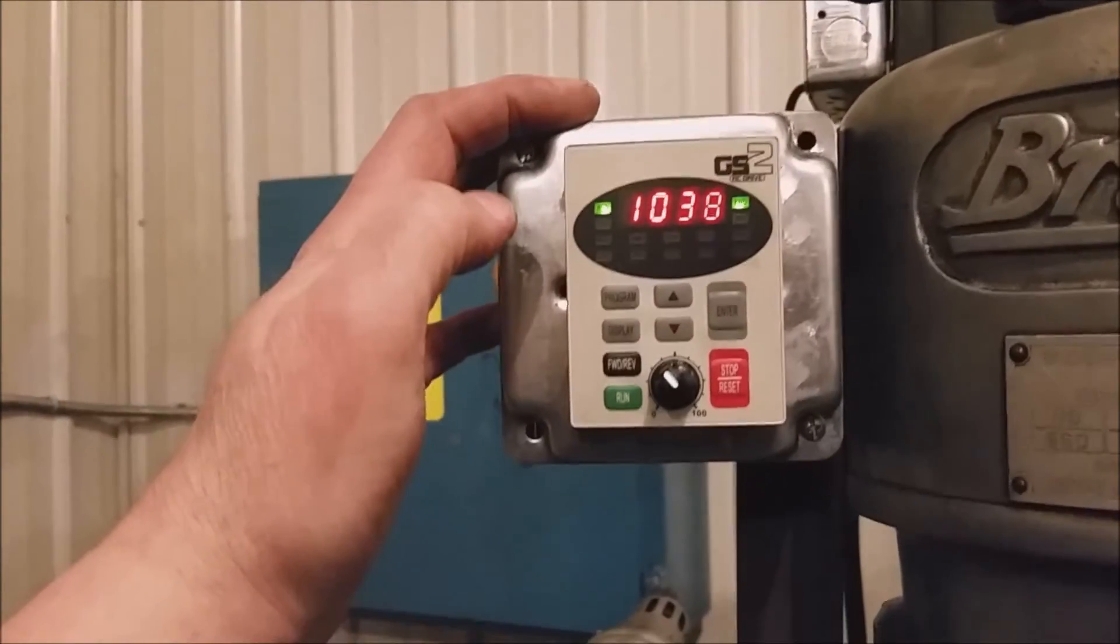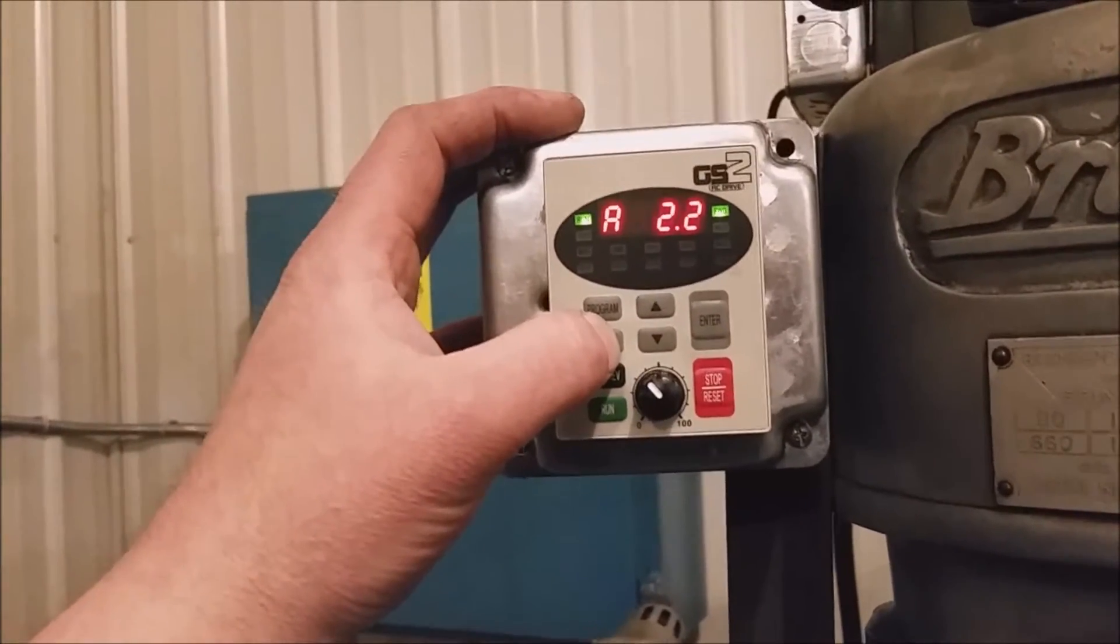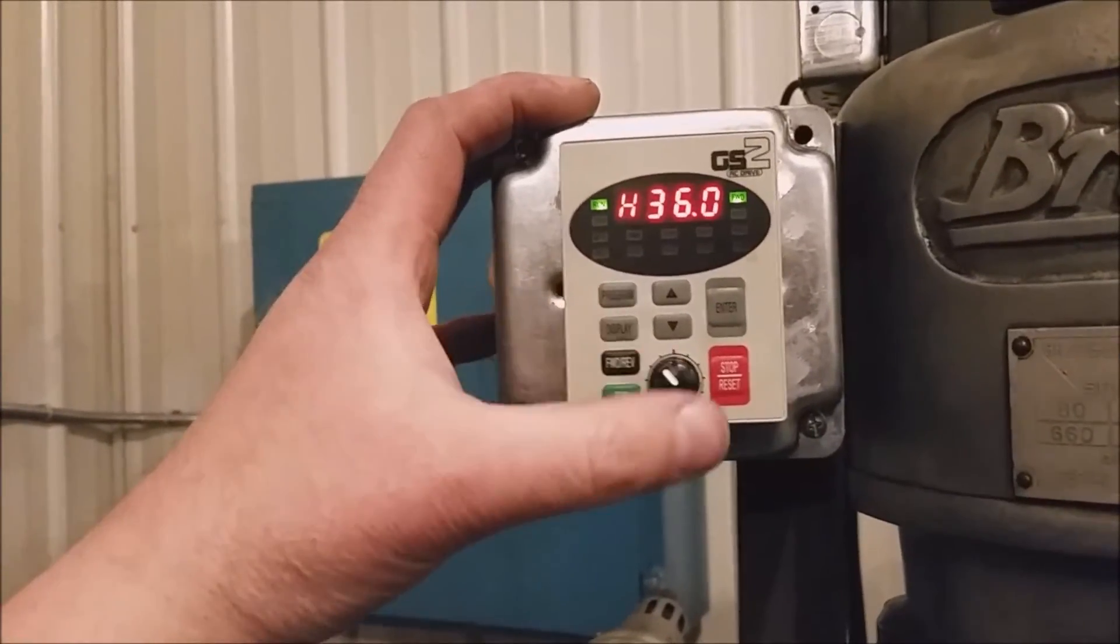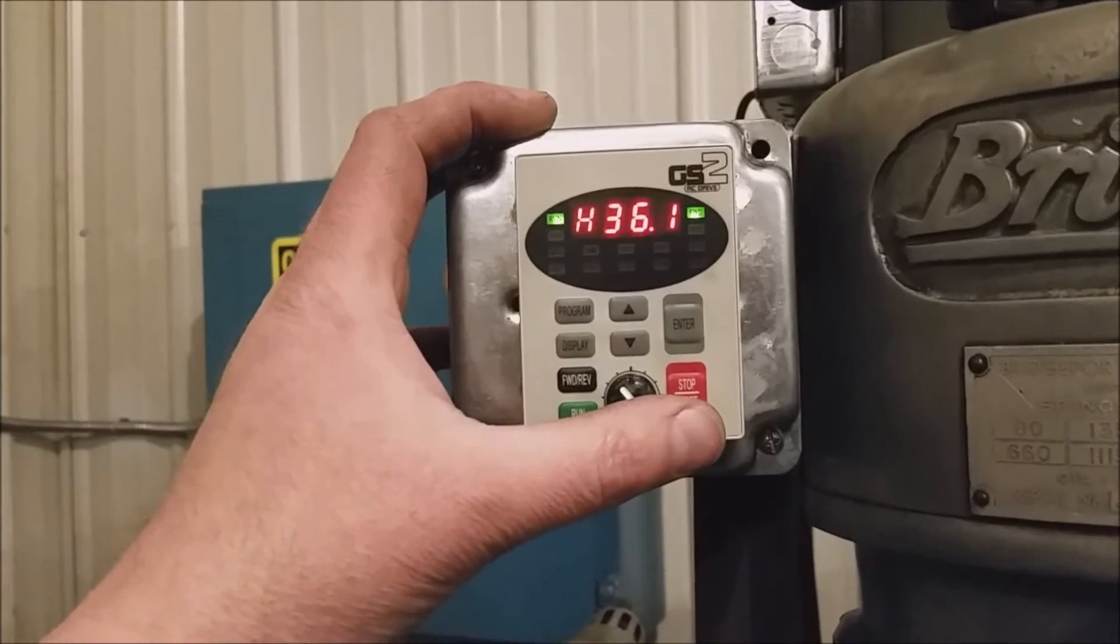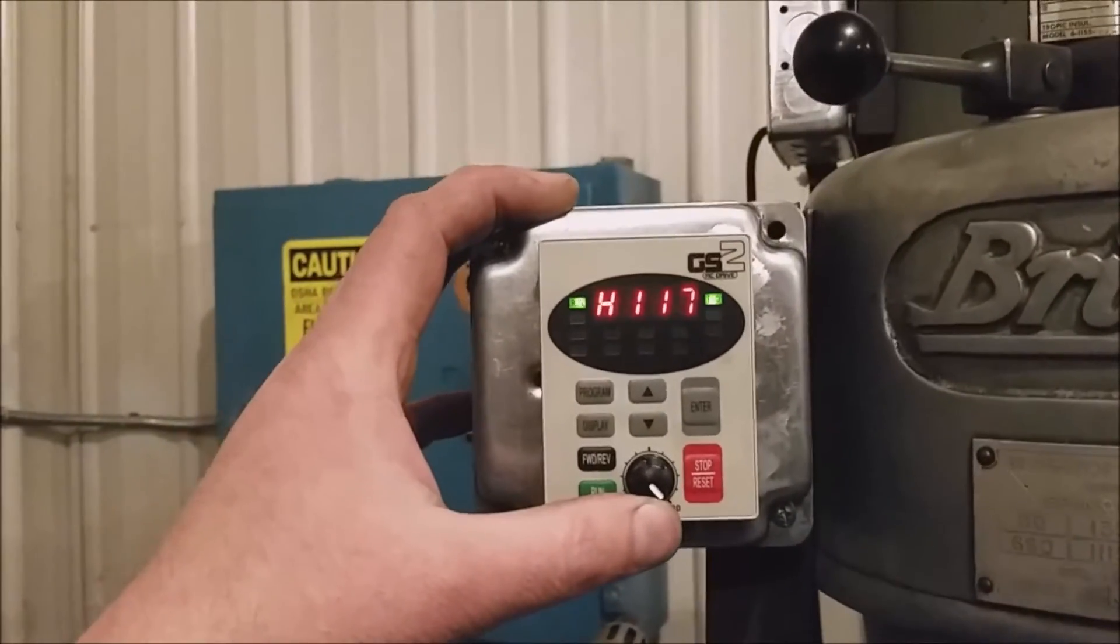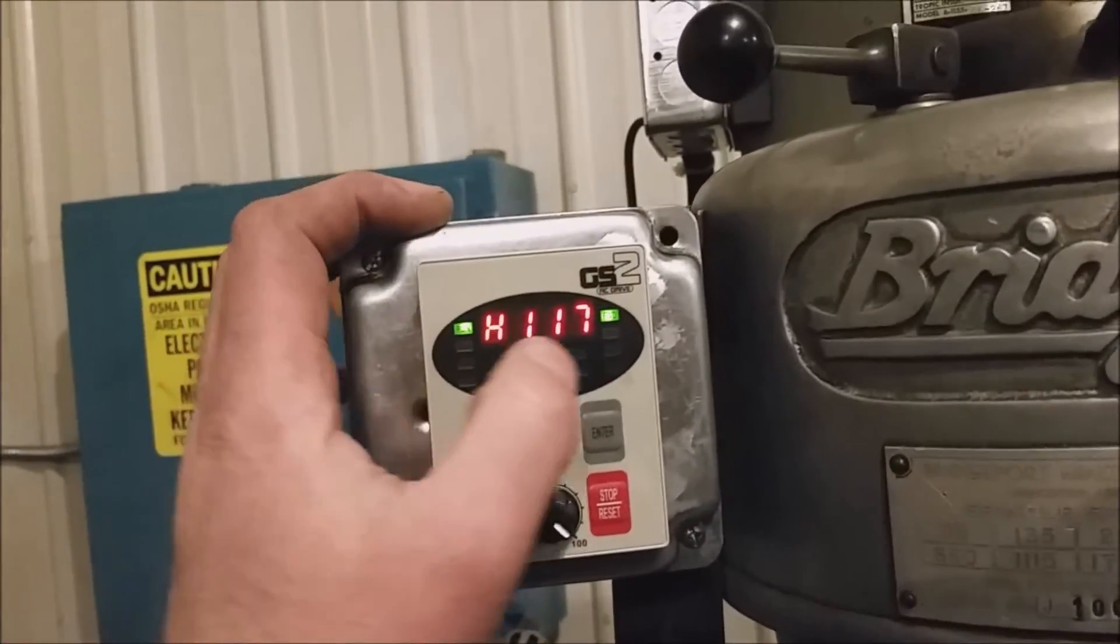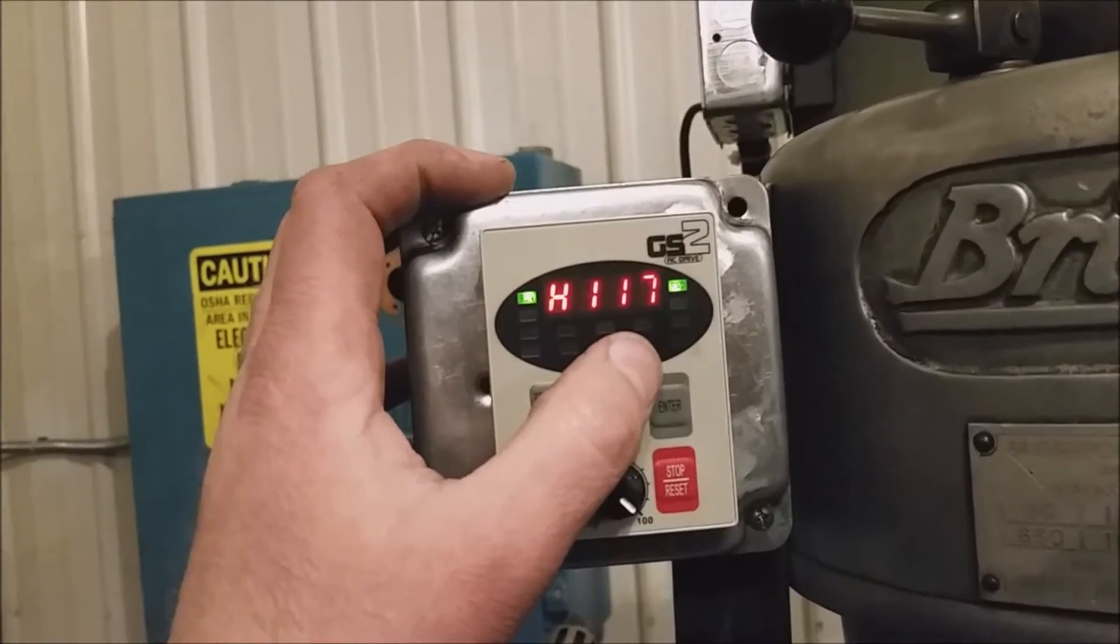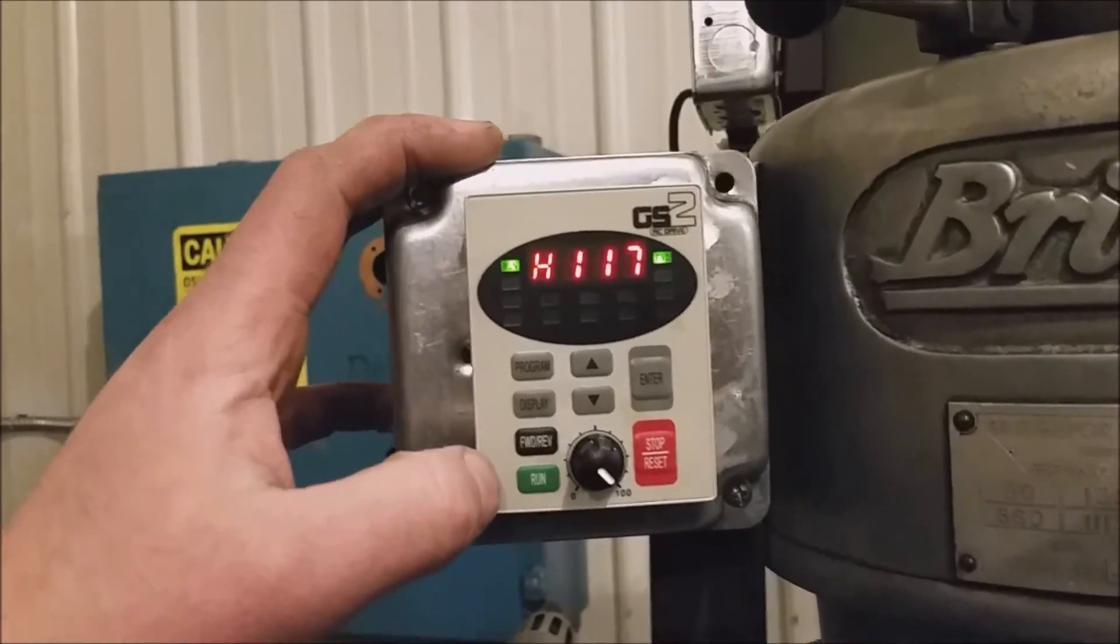You can toggle back through all this. I over-sped mine right now by 2x, so I can go up to almost 120 hertz. I think how it arrives at this number here is just by the maximum RPM that you put in. That's how it arrived at that number, was by the maximum RPM versus the standard RPM.